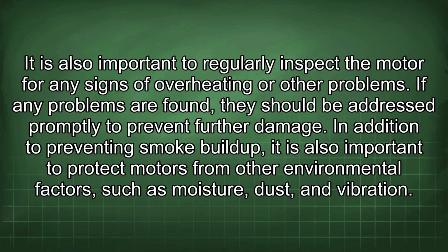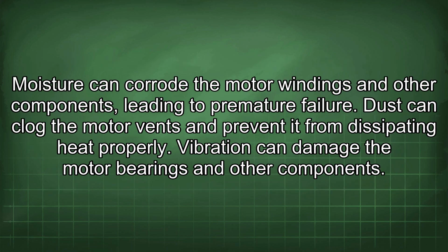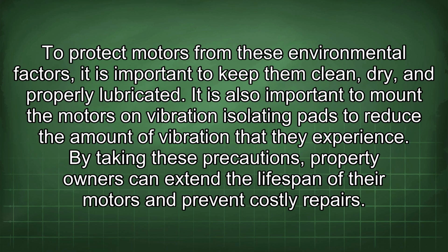In addition to preventing smoke buildup, it is also important to protect motors from other environmental factors, such as moisture, dust, and vibration. Moisture can corrode the motor windings and other components, leading to premature failure. Dust can clog the motor vents and prevent it from dissipating heat properly. Vibration can damage the motor bearings and other components. To protect motors from these environmental factors, it is important to keep them clean, dry, and properly lubricated.